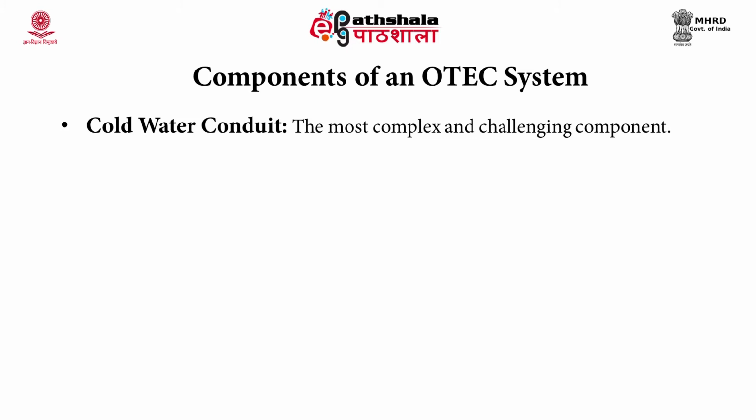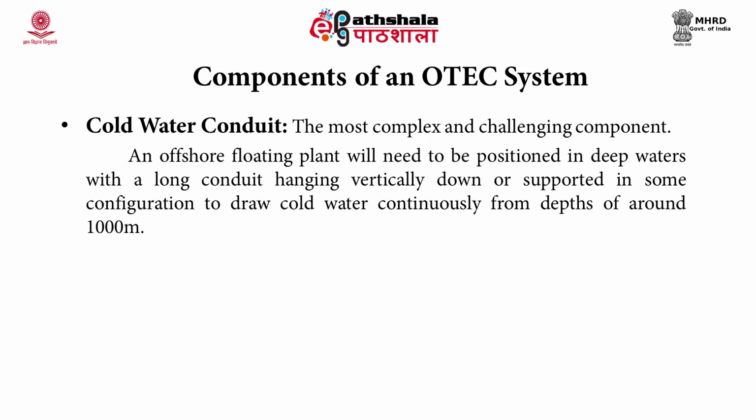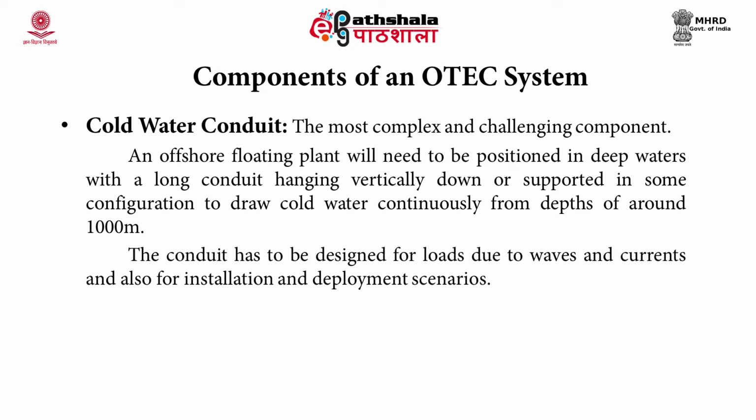Cold water conduit is another component. It's the most complex and challenging component of the OTEC cycle. An offshore floating plant will need to be positioned in deep waters with a long conduit hanging vertically down or supported in some configuration to draw cold water continuously from a depth of around 1000 meters. The conduit has to be designed for loads due to waves and currents, and also for installation and deployment scenarios.